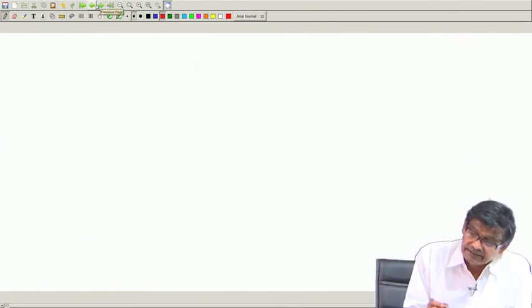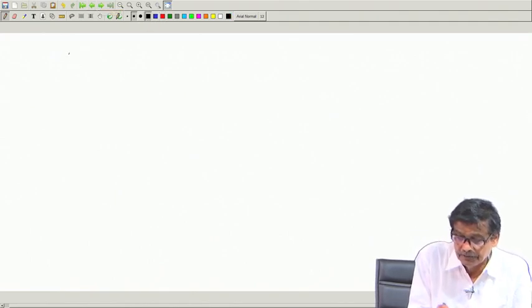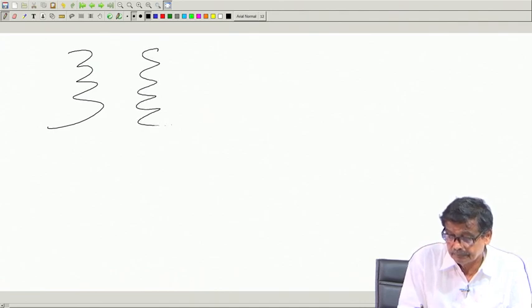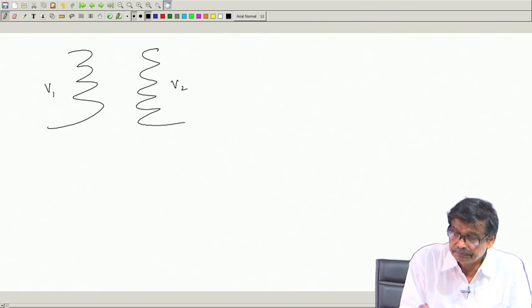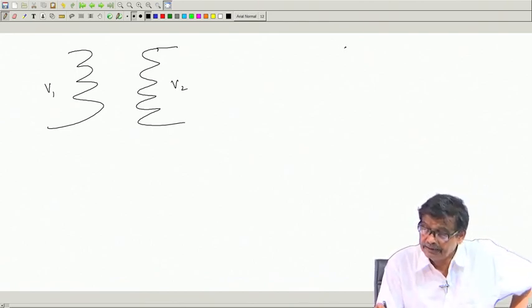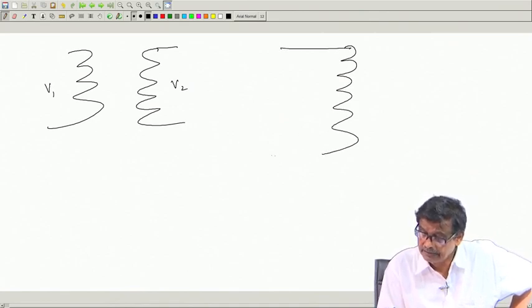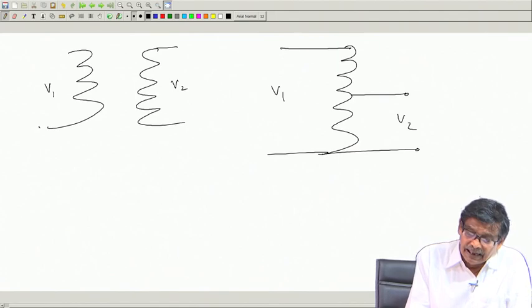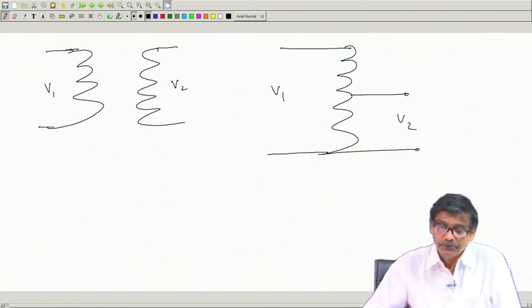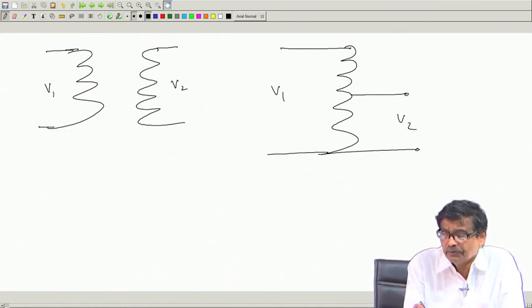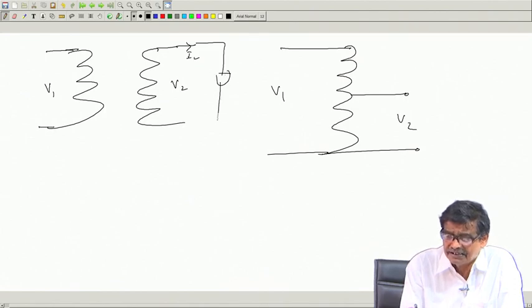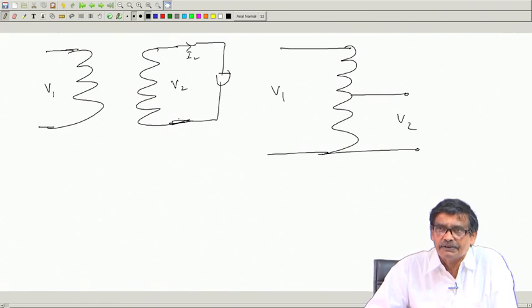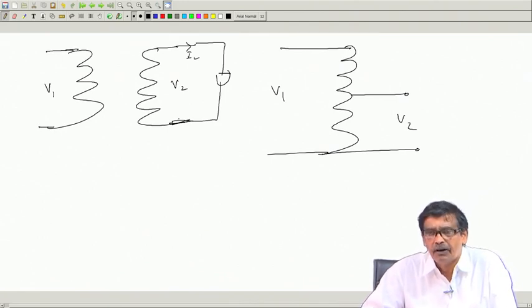For example, suppose you have a two winding transformer giving V1, V2, and a similarly rated auto transformer also giving V1 and V2. Consider a situation where the two winding transformer is supplying load, delivering rated current, because I have purchased a transformer of a given KVA and want it to handle that given KVA, not operate it under no load.